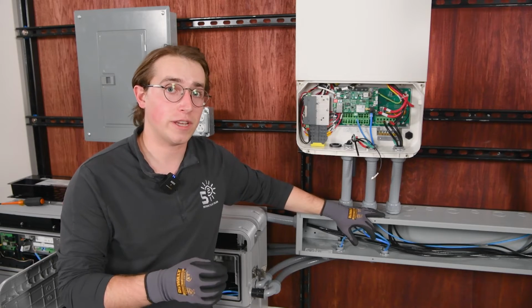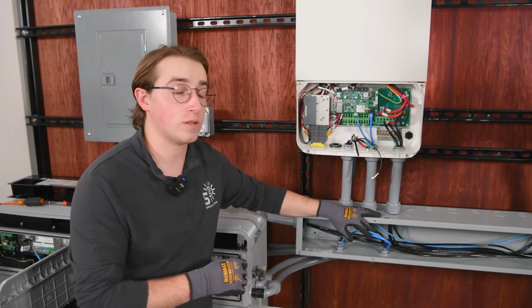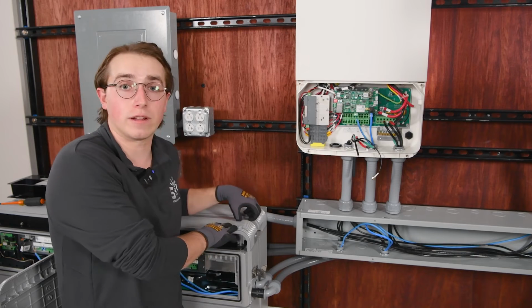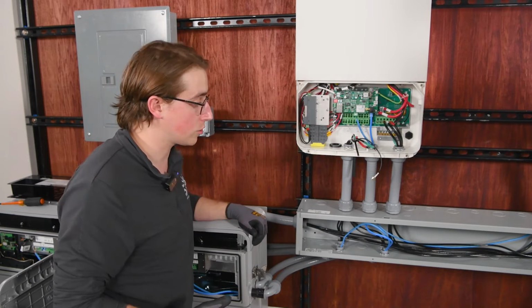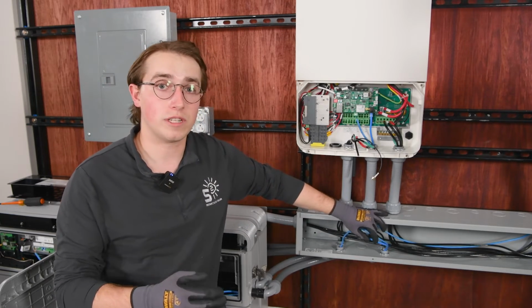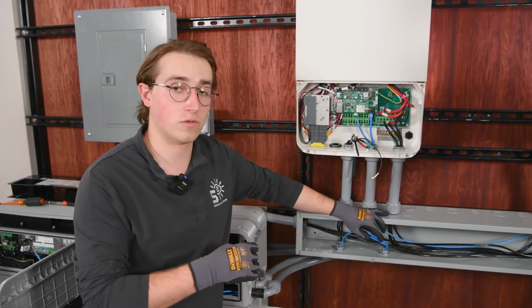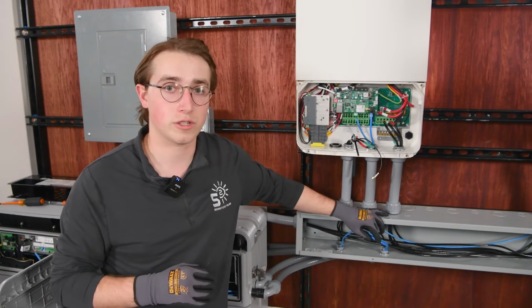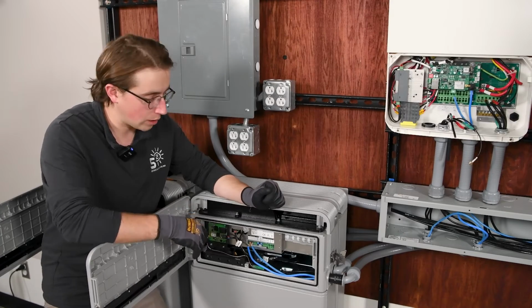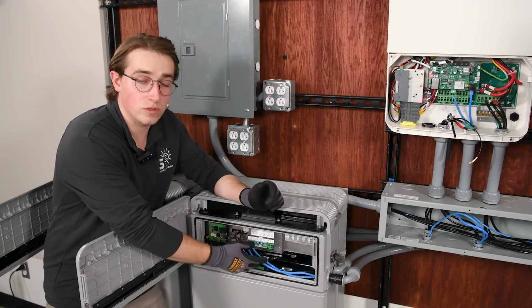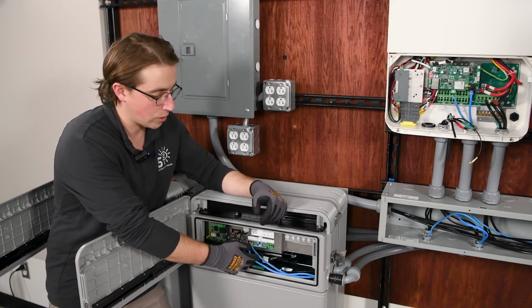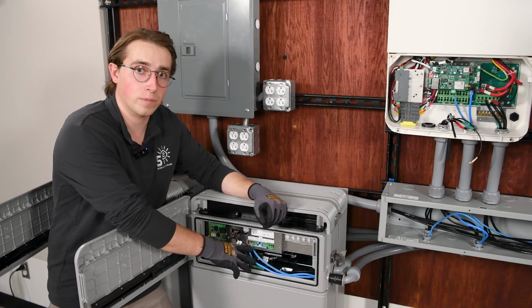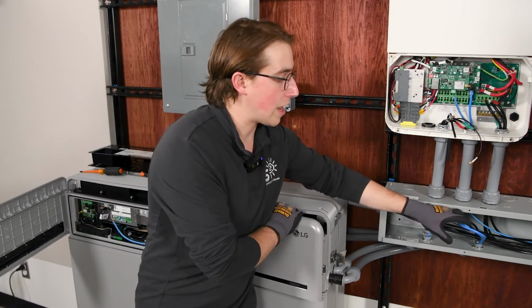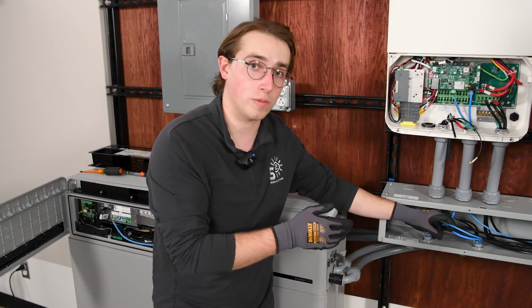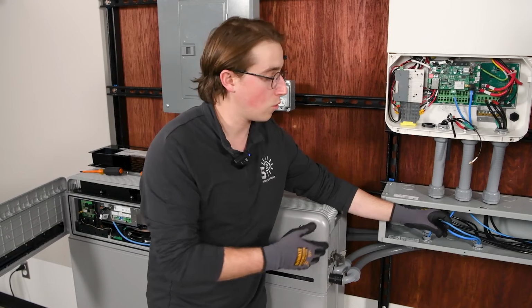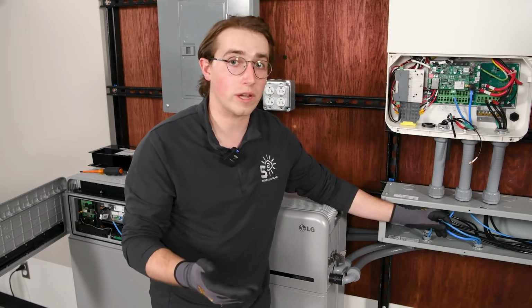Something else to consider with communication cable is interference, especially with high voltage conductors like we have with the LG Prime batteries or PV conductors. Our communication cable will need to be shielded to limit the amount of interference from those high voltage conductors with our communication. For our installation and our setup, we are paralleling our communication cables from our primary battery and our inverter to battery communication cable within the secondary battery. Something else that you can do is actually splice into and parallel the communication cables in your wire trough or your combiner box with a standard Wago connector.